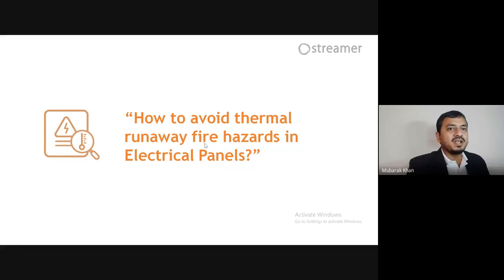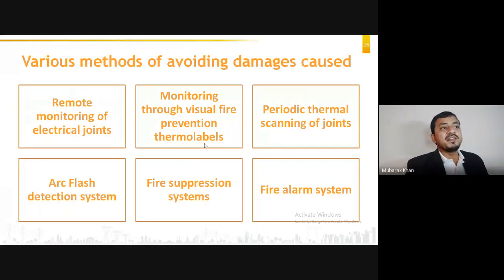Now let us see how to avoid thermal runaway fire hazards in electrical panels. There are various methods to avoid the damages caused. There is remote monitoring of electrical joints. It is being done by continuous temperature monitoring through various techniques, or overheating monitoring through various techniques, or monitoring through visual fire prevention thermolabels. Some people have promoted that you can install temperature stickers on the joints, and if the joint gets heated, the color of the sticker will change. So if you open and see it, you will know that during the operation this was heated. So you can take a corrective action. So this is known as the visual fire prevention thermolabels.